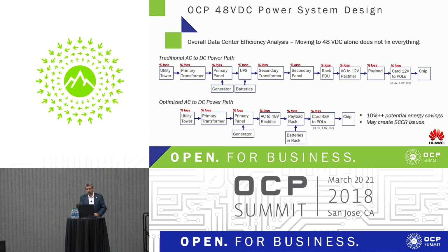Now, when you do this, when you reduce your secondary panels and the other stuff, now you're actually creating short circuit current rating issues, which you might want to look at. We looked at that in our design, and I'll talk a little bit more about it downstream. But again, the potential savings is real. It's, like I said, easily 10%. We can argue that it's more than that. And it's worth considering as you're designing the next generation data centers.